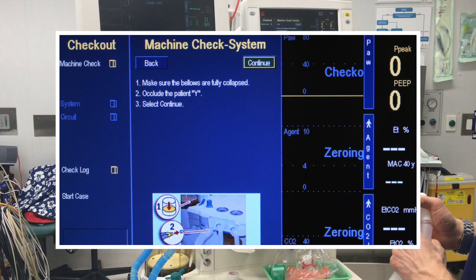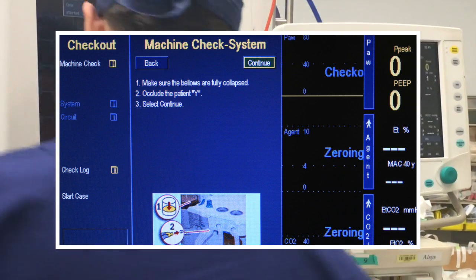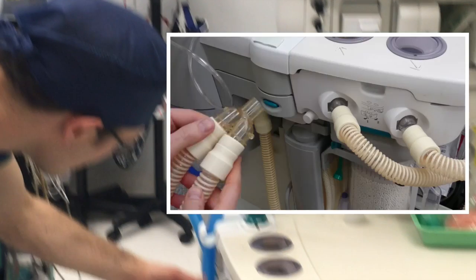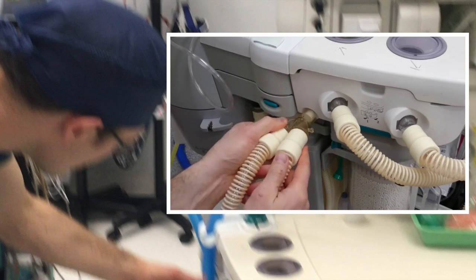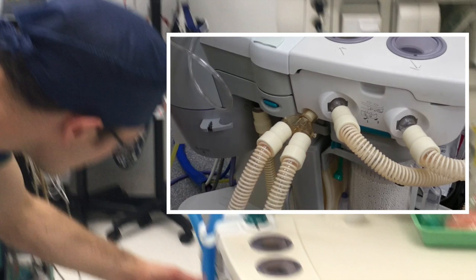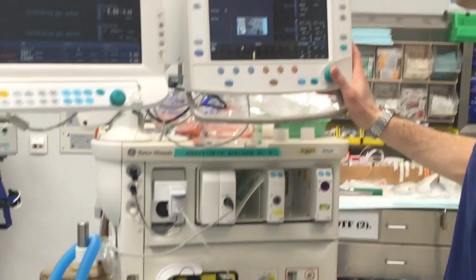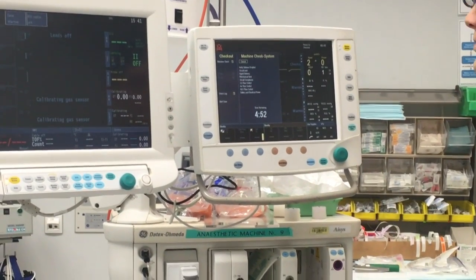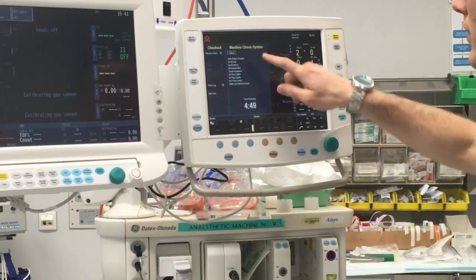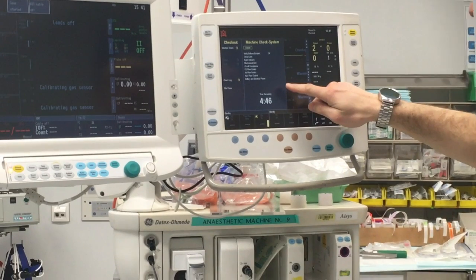The machine then asks you to occlude the patient Y-piece before confirming the next step. This is done by using the stopper shown on the side of the machine. The next step in the automatic check can then be confirmed. This part of the self-check takes the machine about 5 minutes, so fast forward it.